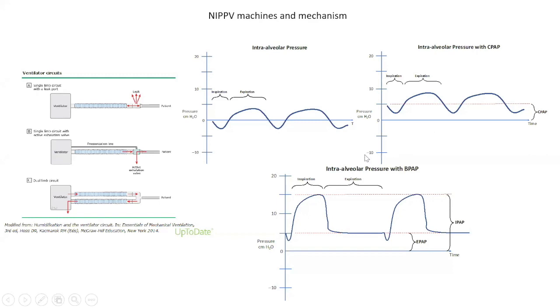Now if you move over to the CPAP graph on the right, what CPAP does is deliver a constant pressure, and that's depicted by this red line. I've chosen a pressure of 5 centimeters of water, which is often a pressure that you would use to start on a patient. The waveform, which depicts the pressure waveform of the patient's breathing, looks exactly the same as it would under normal breathing circumstances. This highlights that patients are initiating all their breaths, breathing spontaneously, but it shifts this curve upward so it's fully positive pressure. The aim is hopefully to re-recruit collapsed areas of lung and improve mismatching of perfusion and ventilation in the lung. It's called VQ mismatch, and the aim of this is really to address hypoxemia. And there's one pressure with CPAP.